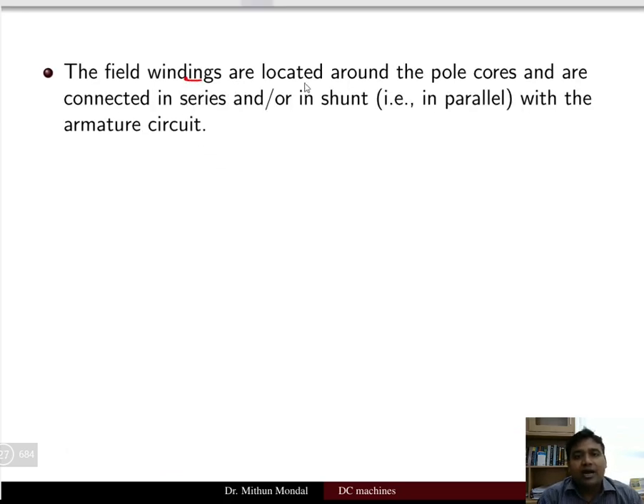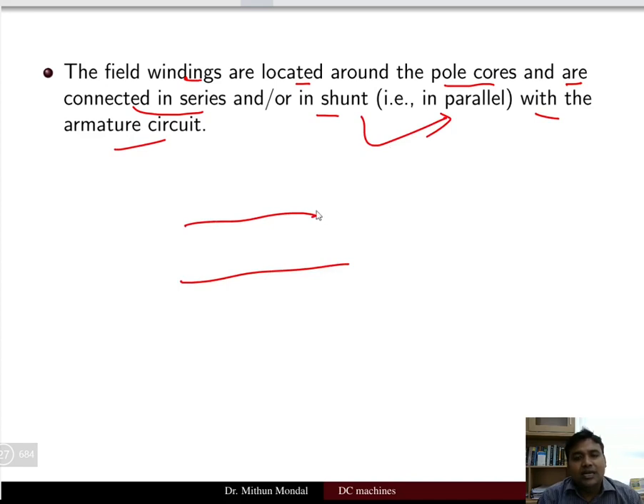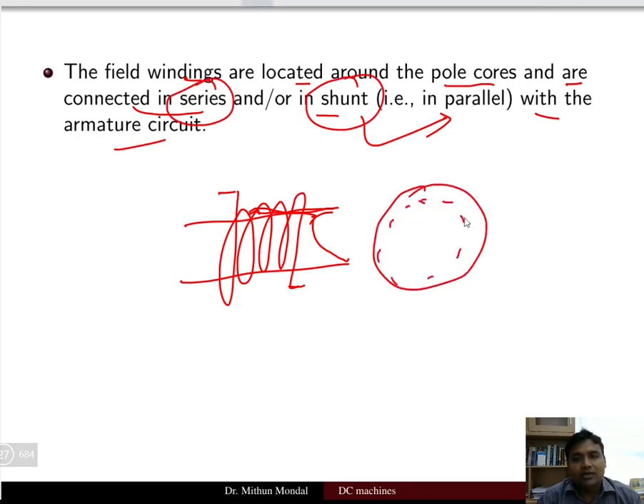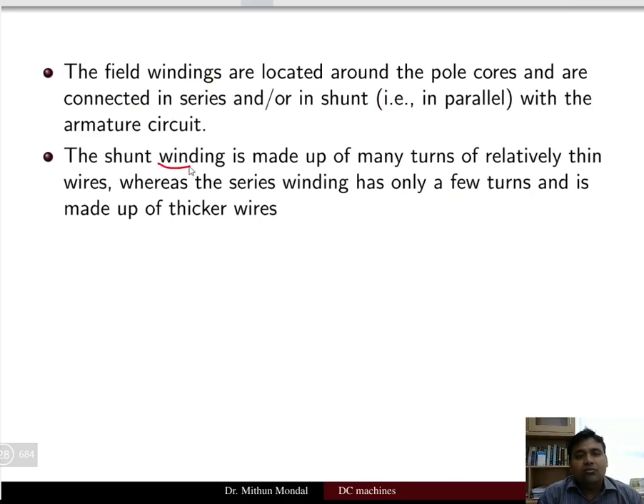The field windings are located around the pole cores and are connected in series or shunt (parallel) with the armature circuit. The shunt winding is made up of many turns of relatively thin wire, whereas the series winding has only a few turns and is made up of thicker wire.